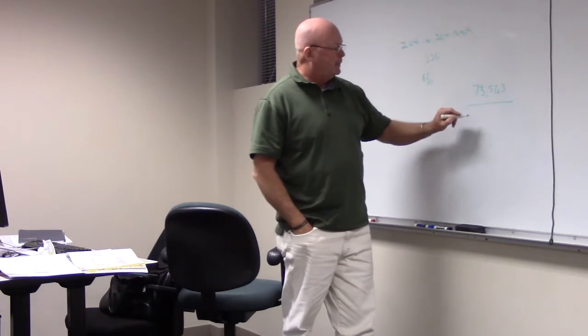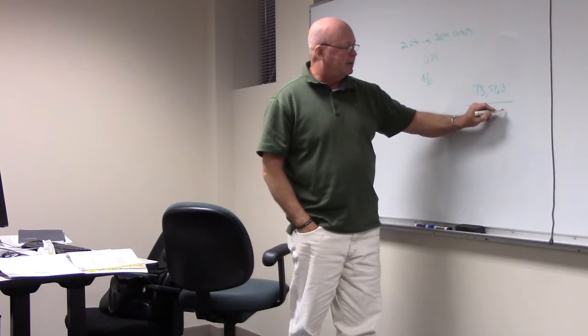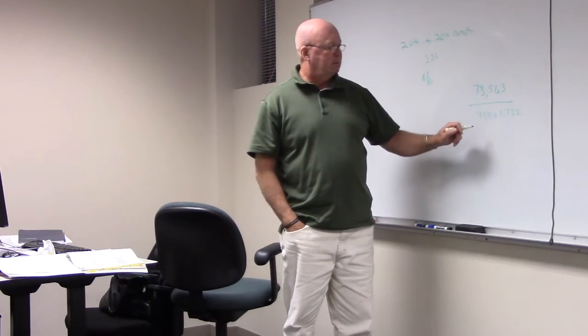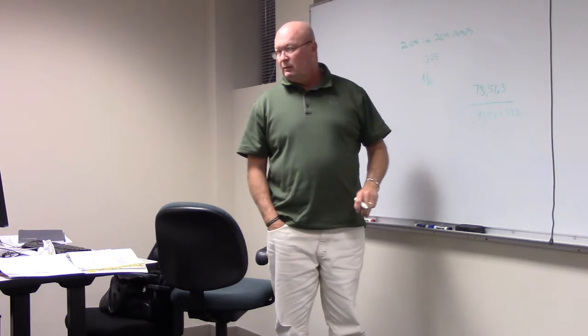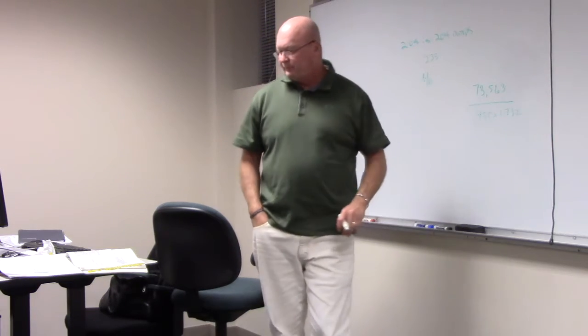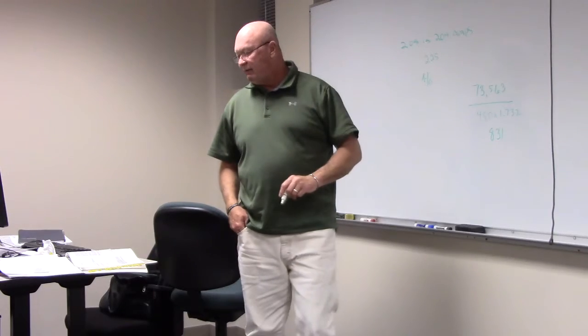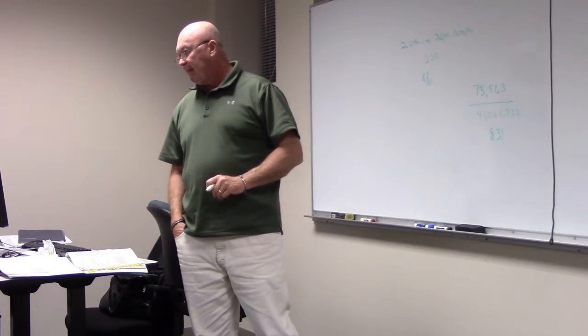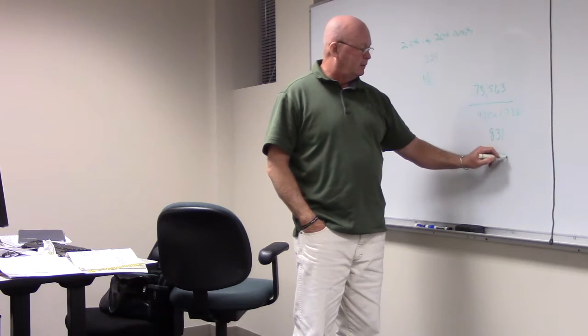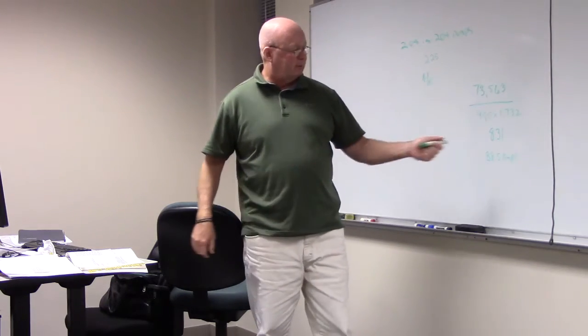Yes, sir. Now we're going to divide that same number. A few minutes ago, we did 208, but now we're going to do 480 times 1.732. Now this is also three-phase. See how much that comes to? 480 times 1.732 is 831.36. 831. Now we're going to divide that into 73,563 and see what we come up with. 88.58. Very good. That's what's feeding the transformer.